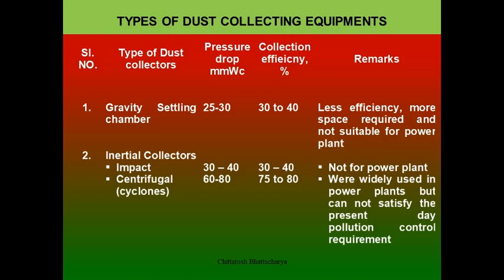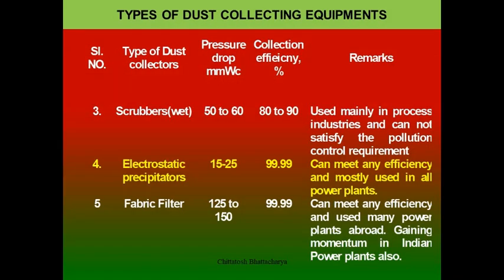There are different kinds of dust collecting equipment which are installed depending upon the particulate matter size, their percentage of collection required and how much emission can be allowed. There are gravity settling chambers, inertial collection which may be centrifugal type or scrubbers, electrostatic precipitators, and fabric filters. All these can be employed depending upon the collection efficiency, economic criteria, and how much pressure drop is allowed across the flow passage.